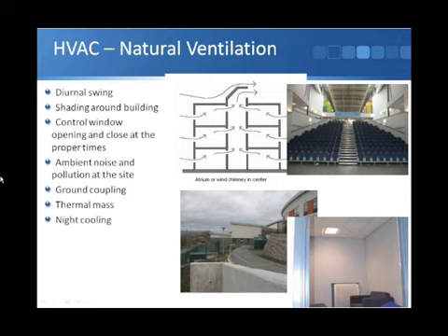Looking at heating and ventilation and air conditioning, I guess one of the starting points for many of us is, can we use natural ventilation instead of a ventilation and air conditioning system? If we can't use it in the summer, perhaps because the temperature is too hot, can we use it part of the year in the winter? So we completed a building in Chicago which is naturally ventilated for 9 months, and then it has a hybrid ventilation system which comes in and supports the natural ventilation through the 3 months of hot and humid weather. As a result of doing that, we have a building which is using 50% of the energy consumption of comparable buildings in the States. So it's quite a big advantage. So again, it's trying to think across the whole year rather than just trying to design for peaks.